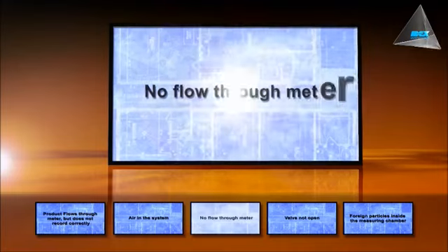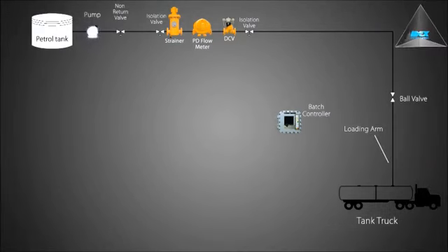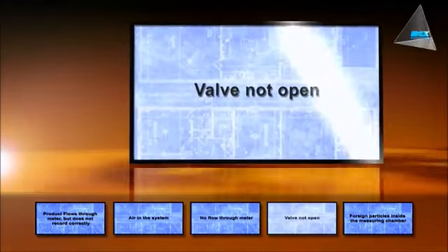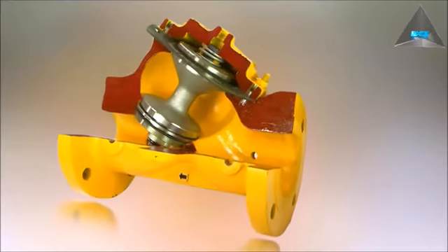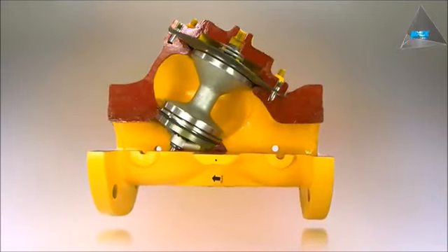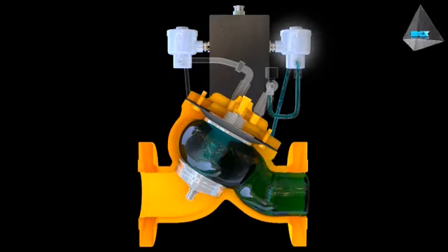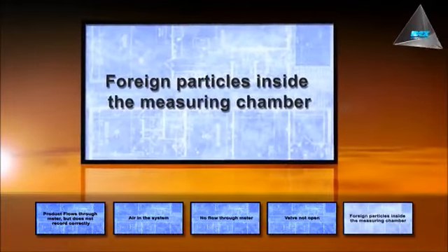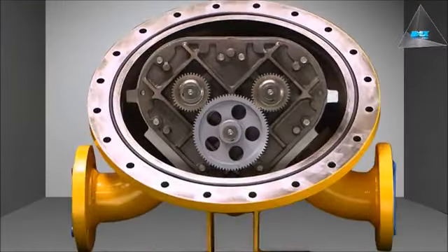No flow through the meter. Possible cause: faulty pump. Solution: check the pump and repair or replace as required. Valve not open. Solution: check valve internals and check the functionality of the valve solenoids and clean if required. Foreign particles inside the measuring chamber. Solution: clean the meter.